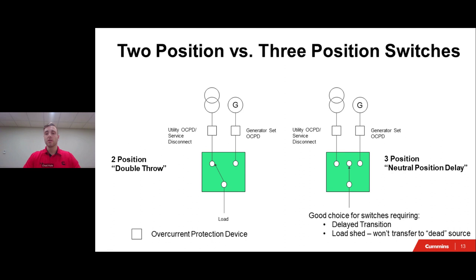So I mentioned it a little earlier on in the presentation, but we have something that is called a two position versus a three position switch. And I will briefly get into the differences of those two here in just a second. So when referring to a two position transfer switch, whether that's in a spec sheet or in a piece of material, they are commonly referred to as a double throw switch or a neutral position for a three position switch.